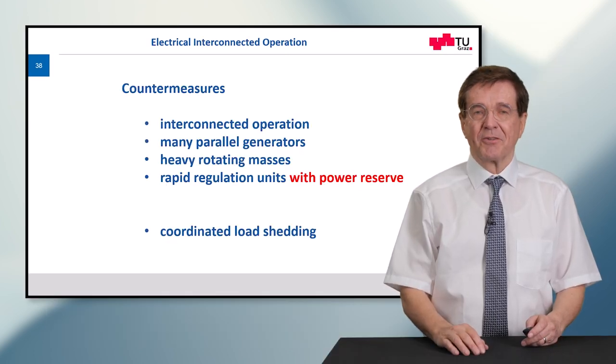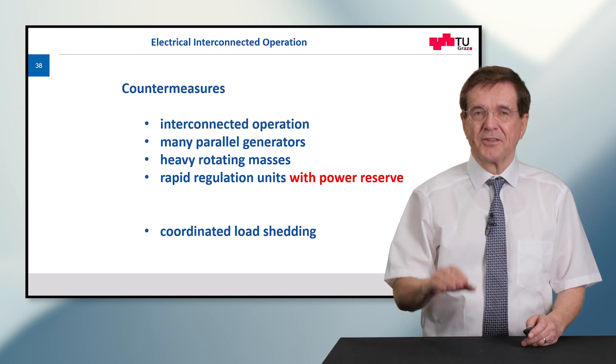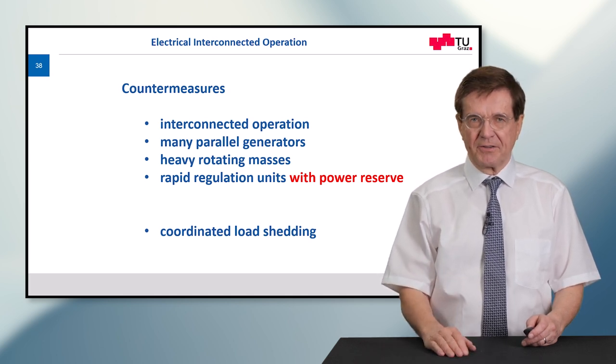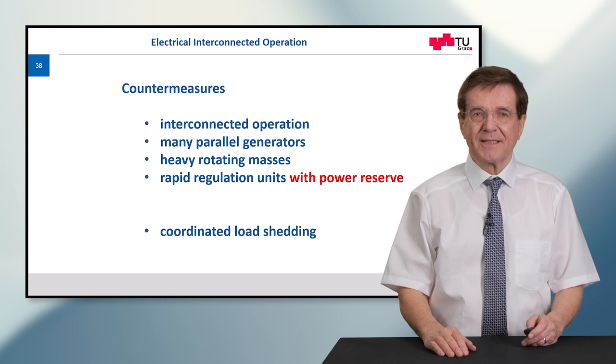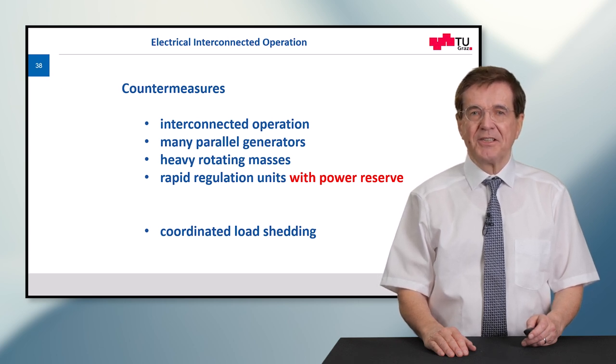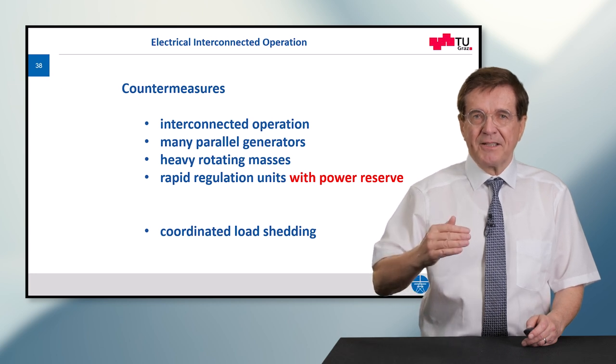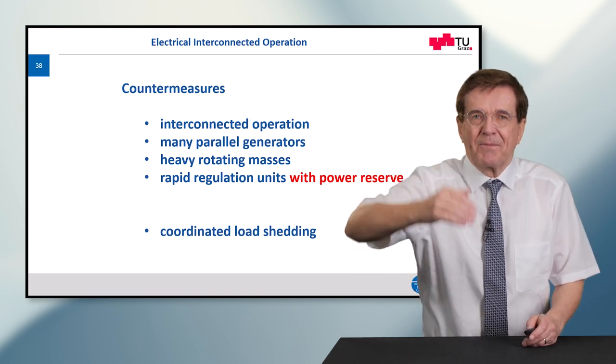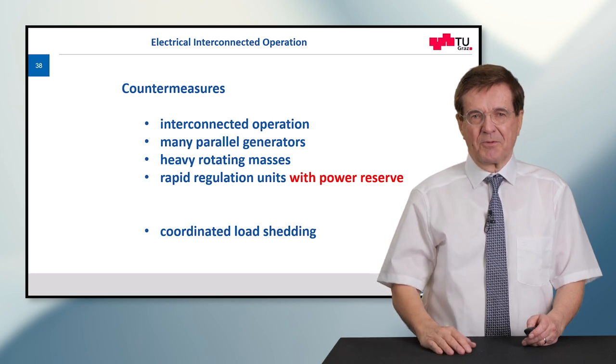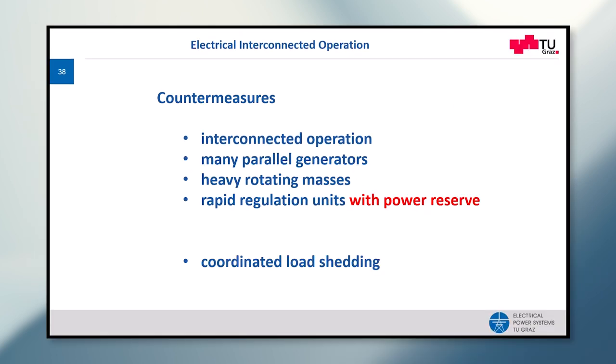So what can be done against this? The countermeasures are first interconnected operation of many parallel generators, heavy rotating masses, and rapid regulation units with power reserve. So there must be generating units that can speed up and step up their power output. The coordinated load shedding is meant to balance the consumption of electric energy with the output of the generating units.